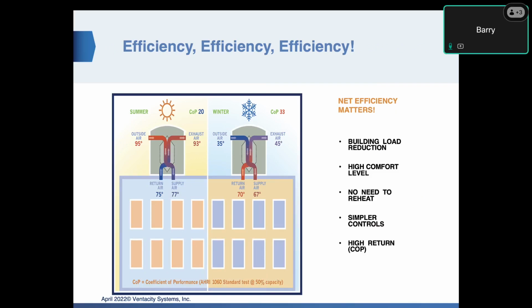And what we're looking at here, if you're familiar with COP or coefficient of performance, most people are familiar with heat pumps, which have a coefficient of performance of, say, 3 on an average, 3.5. What that means is 1 watt of energy in gives you 3 or 3.5 watts of heating or cooling out of that heat pump. With electric resistance heat, you put 1 watt into an electric baseboard, and you get 1 watt of heating. It's a COP of 1. So what we're looking at here is our fans are using very low energy, and the recovered energy is very high. So you have the COPs of up to 20 at design temperature here in the summertime, up to 33 in the wintertime. We've seen it even higher in extreme temperature differences. The higher the temperature differential, generally the more energy you're recovering.